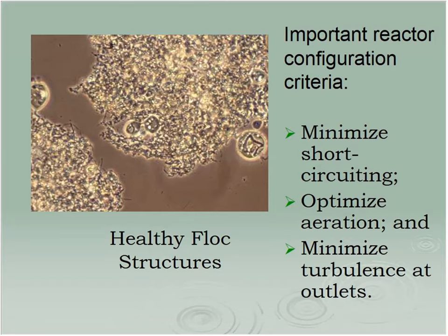So again, what we want to promote through all of this process, and when you look at mixed liquor in your tank, you should be able to identify this. This is our flock. Nice, strong flock particle, very clear supernatant around it. That's what we want to see. That's why mechanical aeration is not exactly ideal. You've got to chop that up. It doesn't take much to break this apart. Minimize that turbulence.